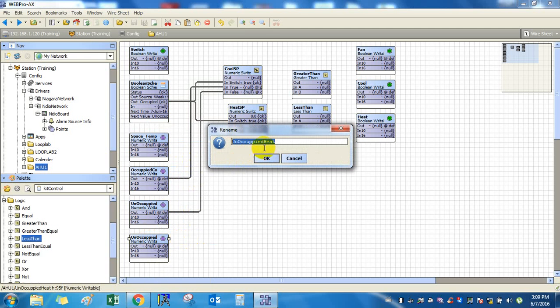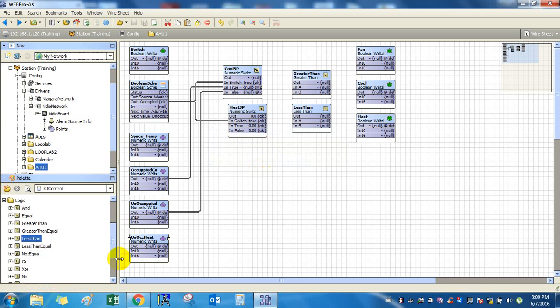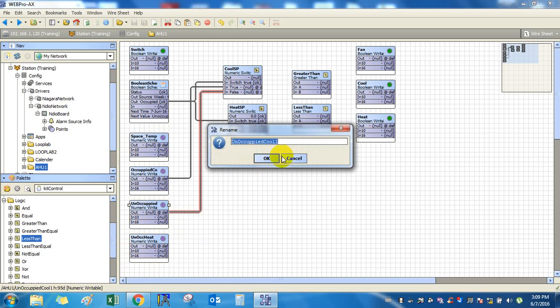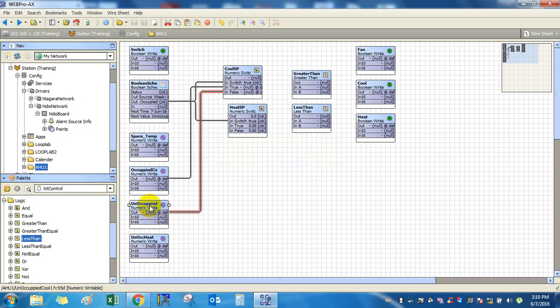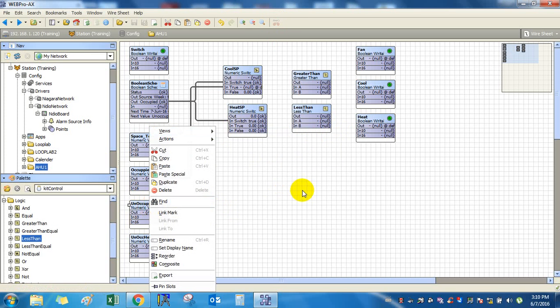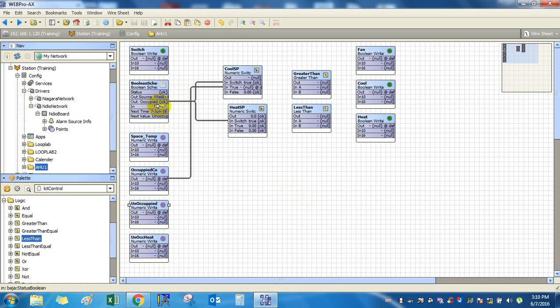Change the facets to degrees Celsius for both the switches. So these two blocks will tell what your cooling set point or heating set point is at the moment. Then you have to compare these set points with your space temperature to decide whether your unit is in heating mode or cooling mode. So link the space temperature to your greater than block, input A. Whenever your space temperature is greater than your cooling set point, that means you need cooling in the space.